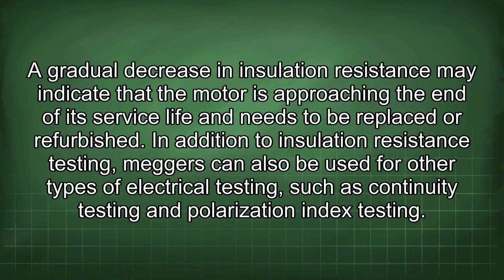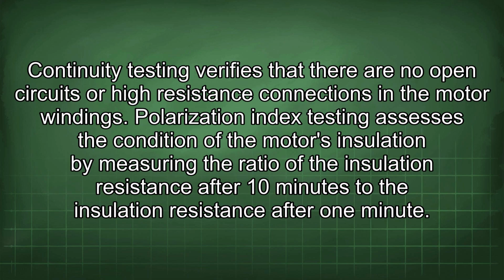In addition to insulation resistance testing, Meggers can also be used for other types of electrical testing, such as continuity testing and polarization index testing. Continuity testing verifies that there are no open circuits or high resistance connections in the motor windings. Polarization index testing assesses the condition of the motor's insulation by measuring the ratio of the insulation resistance after 10 minutes to the insulation resistance after 1 minute.